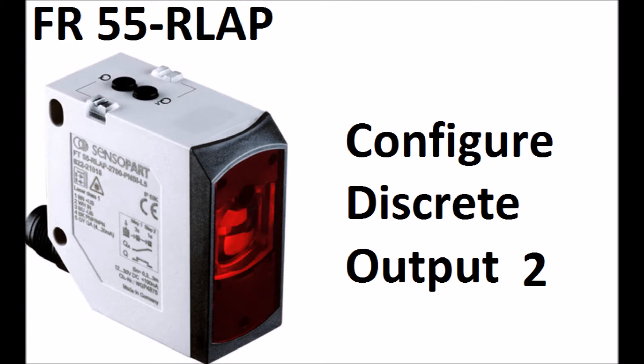To configure discrete output two, it's much the same as output one, except you press and hold the button for six seconds at the beginning. So here, we press and hold, and at three seconds, you'll see the lights flash slowly. We keep holding it. At six seconds, they'll flash faster. There we go. Now we can move the target or not, depending on window or point mode. And the second step, tap the button.